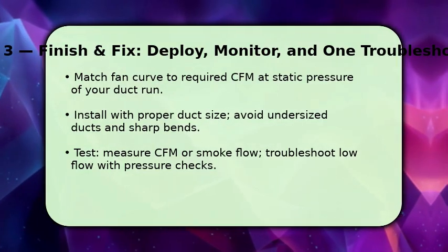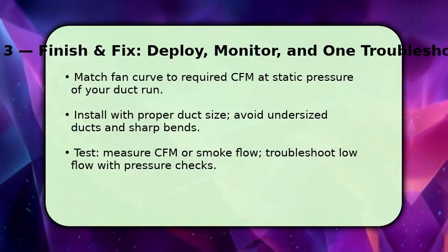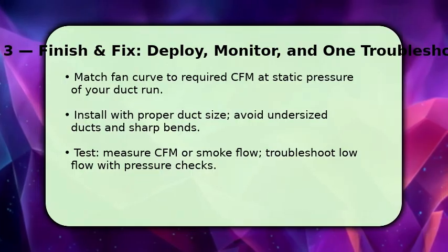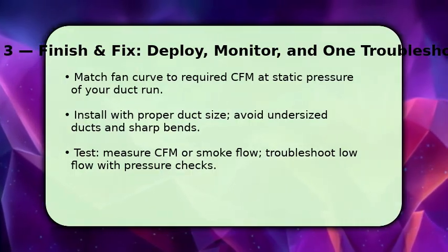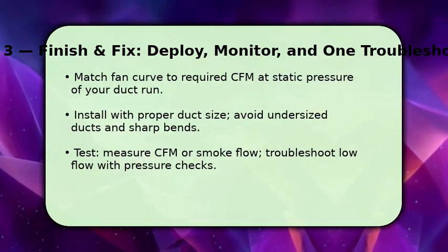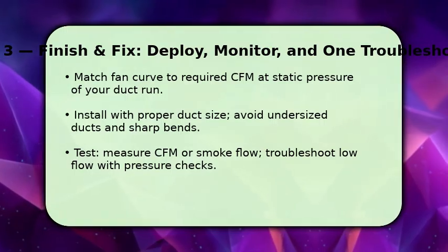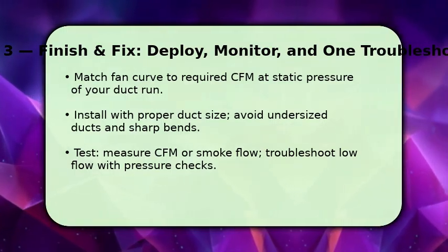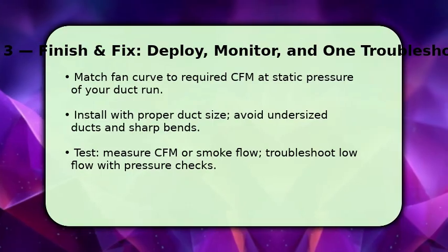Once installed, use correct duct sizing and smooth transitions. Undersized ducts or sharp bends kill flow. Finally, test the system with an anemometer or simple smoke test. If flow is low, recheck for blocked intakes, excessive static pressure, or leaks. Those are the 3 most common issues to troubleshoot.